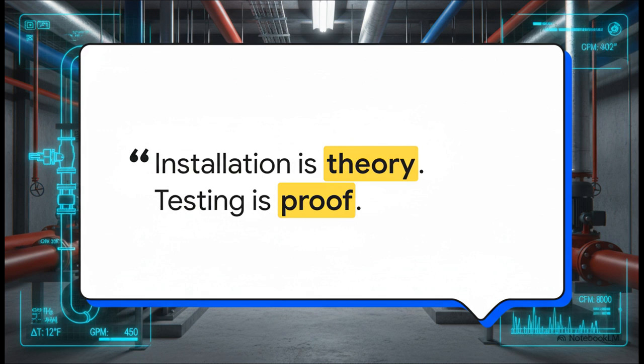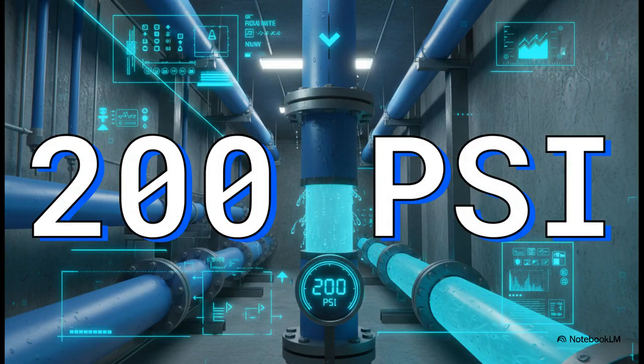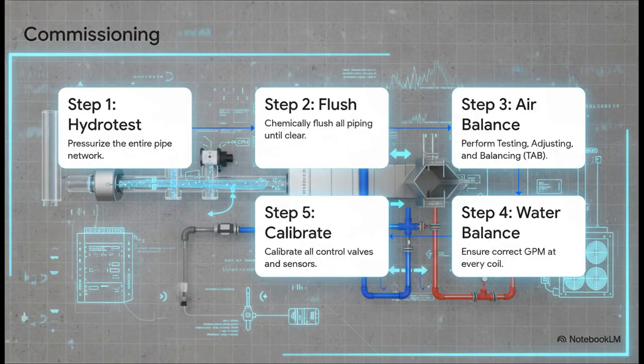Now comes the proof. So, for starters, the entire massive network of pipes is filled with water and then pressurized to at least 200 pounds per square inch. To give you an idea, that's more than 6 times the pressure you have in your car tires. The system has to hold that insane pressure, usually for a full 24 hours without a single drop leaking from any of the thousands of joints. It is the ultimate stress test. After it survives the pressure test, the system has to run what we call the commissioning gauntlet. You can see the steps here.